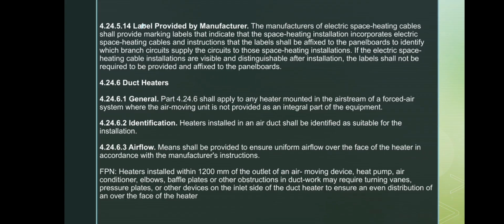Next, for duct heaters. These rules apply to heaters mounted in the airstream when the air moving unit is not built into the heater. Duct heaters must be identified as suitable for duct installation, and there must be a way to ensure even airflow over the heater surface. If the heater is installed close to elbows, air conditioners, or obstructions, additional devices like turning vanes or pressure plates may be needed to distribute the airflow properly.